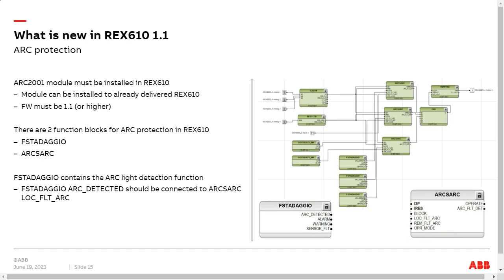The main difference is that if you take a look at the arc function block, the one on the left, this FSTA, DA, GGIO, as you see, there are 4 outputs. Arc detected, the name says it directly, means it has picked up an arc, so that output will go high. Then the lowest one, sensor fault, means, for example, that the supervision of the sensor has encountered an issue, if it's disconnected or the fiber has been broken.